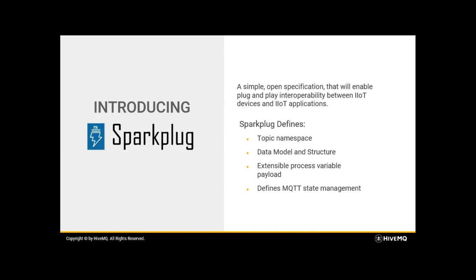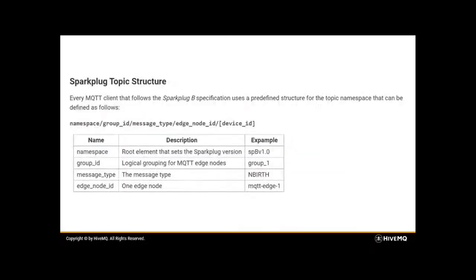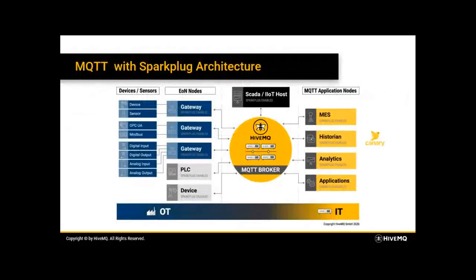In your project, you want to reduce headaches and have an open standard that can be maintained in the future. Sparkplug B is the way to move forward. The Sparkplug topic structure has a namespace, group ID, message type, edge node ID, and device ID — all already defined in the Sparkplug B specification. From there, you don't have to define it yourself.